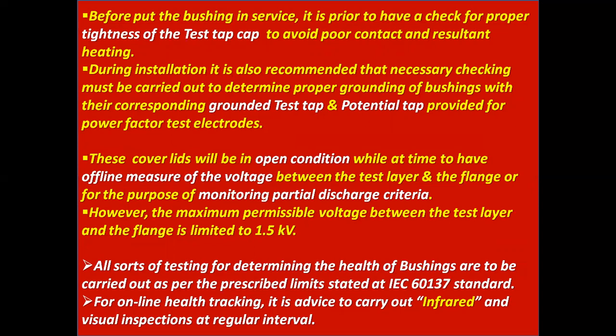These cover lids will be in open condition at the time of offline measurement of the voltage between the test layer and the flange, or for the purpose of monitoring partial discharge criteria. However, the maximum permissible voltage between the test layer and the flange is limited to 1.5 kV.